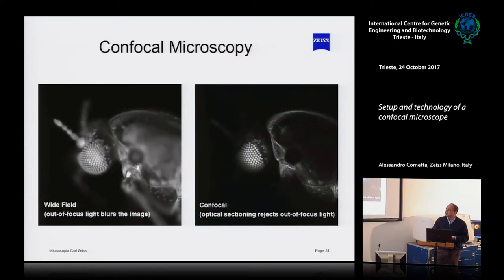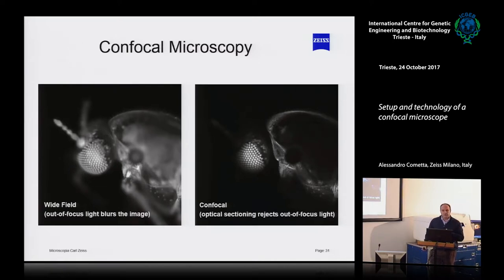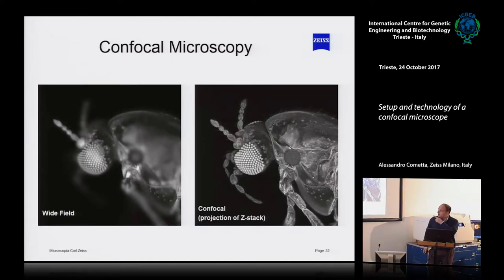Why is the confocal so powerful? Because if I look at a standard sample in wide field, I still get out-of-focus information — it is blurry. In the confocal case, the out-of-focus information is completely removed and can be reconstructed by adding the information from the other planes. For that reason we have much better information.